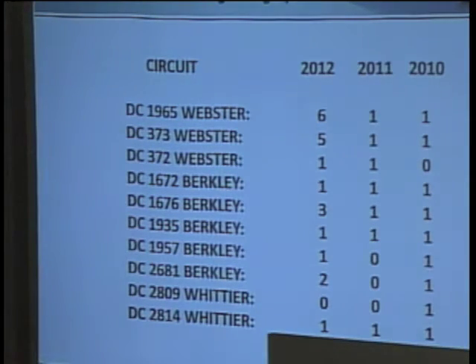From a reliability standpoint, this is approximately how many outages per year per circuit each of the circuits feeding Berkley have experienced. On the Webster substation, two circuits, 1965 and 373, those outages, all three of them, were directly related to the July 17 outage. However, one of them had to be restored and then jumpered or opened and restored again. A couple of those times may have been due to the fact that we didn't have enough capacity and had to shut down the circuit intermittently while we restored others. So there was a time period when each of these had to be interrupted. The work they're doing presently at Webster will eliminate the need to have these interruptions next year.